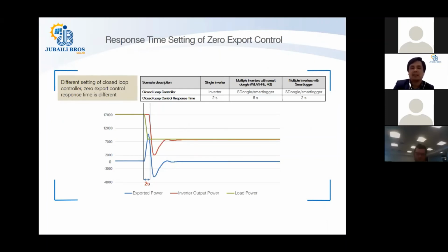Response time setting of zero export. As I said earlier, I have a slide, so this is the one. There are three lines as shown here. The blue line is the exported power, the red one is the inverter output power, and the light green one is the load power. So if you see here, normally when you have a zero export control option, not based on the total power or the single phase power, you also have an option of complete zero export, where no power goes from any phase towards the grid. That is also an option in our inverter.